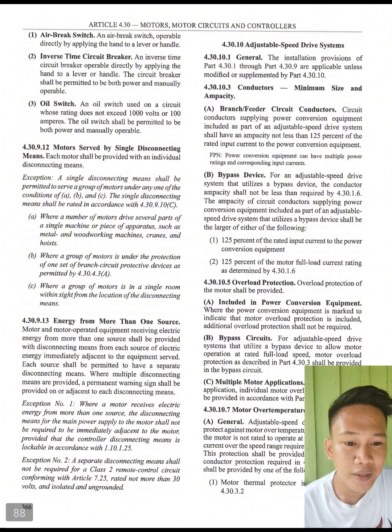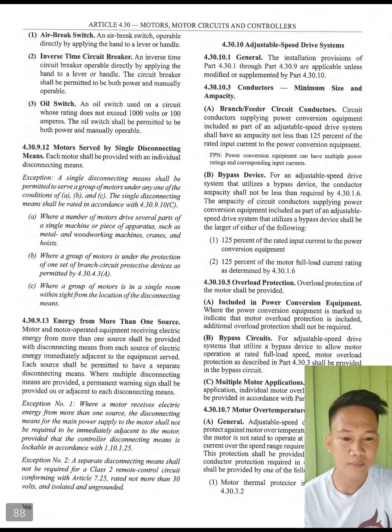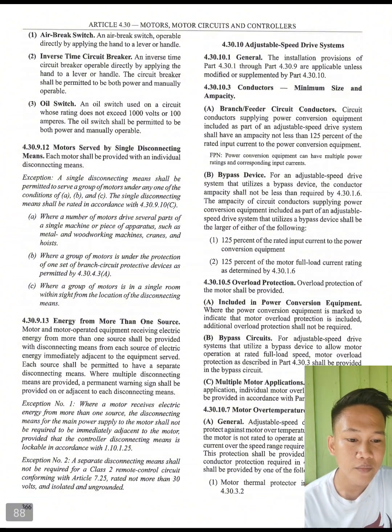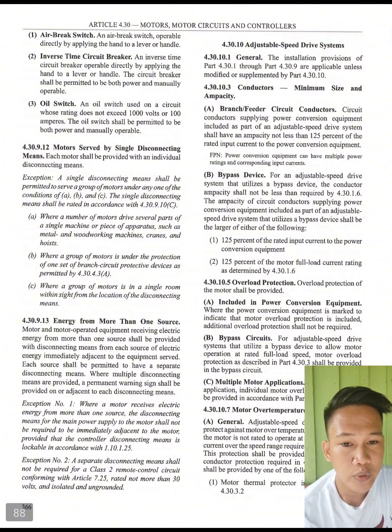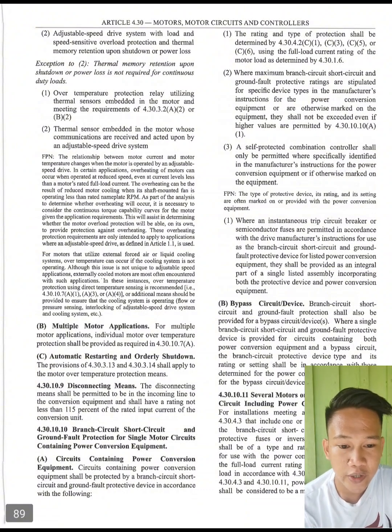So, next is 4.30.10.7. Motor over temperature protection. So, layo tayo motor over temperature protection para malikay o ma-overheat. General, adjustable speed drive system shall protect against motor over temperature condition where the motor is not rated to operate at the nameplate rated current over the speed range required by the application. This protection shall be provided in addition to the conductor protection required in 4.30.3.2. Protection shall be provided by one of the following means. First, we have motor thermal protector in accordance with 4.30.3.2. Second, adjustable speed drive system with load and speed sensitive overload protection and thermal memory retention upon shutdown or power loss. Exemption to 2. Thermal memory retention upon shutdown or power loss is not required for continuous duty loads.